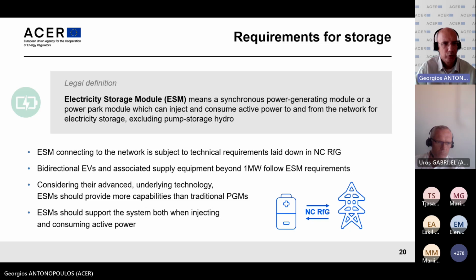As I mentioned before, bi-directional electric vehicles and associated supply equipment beyond 1 megawatt follow the electricity storage module requirements. There are some additional requirements for these devices based on the underlying technology, which is able to provide more capabilities than traditional power generating modules. The electricity storage modules should support the system both when injecting and consuming active power.